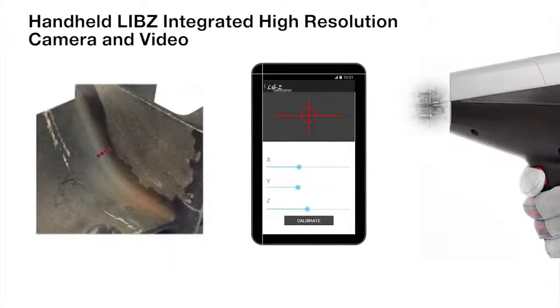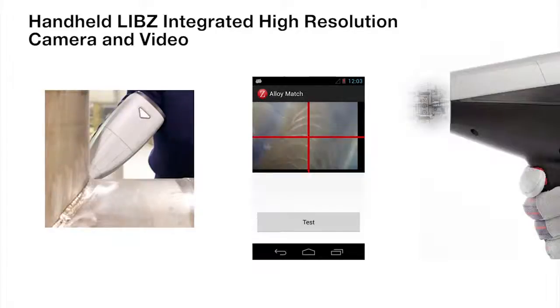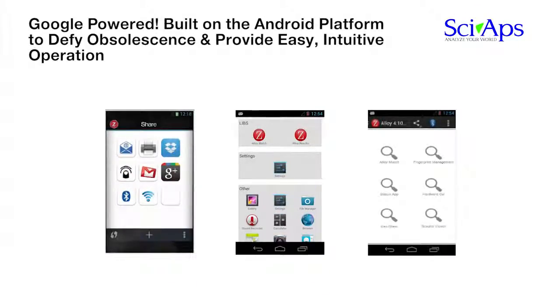The handheld SciAps Z LIBS combines its integrated high-resolution camera and video capability with powerful Android features that enable photos or videos of test locations or samples to be taken and stored with results. The laser is automatically focused to less than 50 micron beam size without requiring any external intensity-killing collimation. Individual chemistries can be saved or averaged, and images of each test point can be saved — precision impossible with handheld XRF or Spark OES.